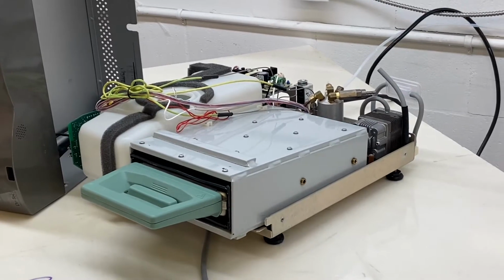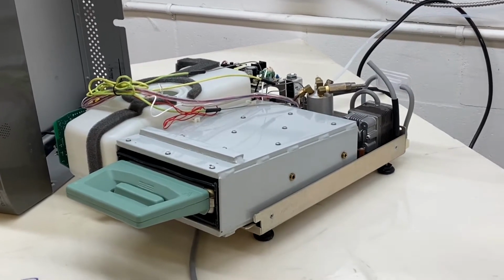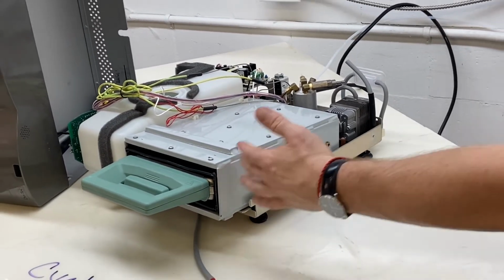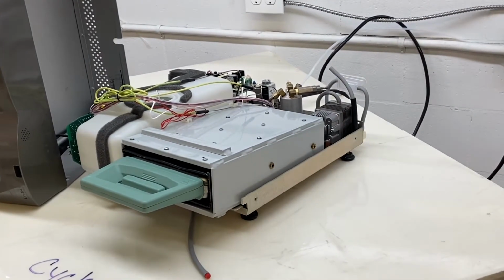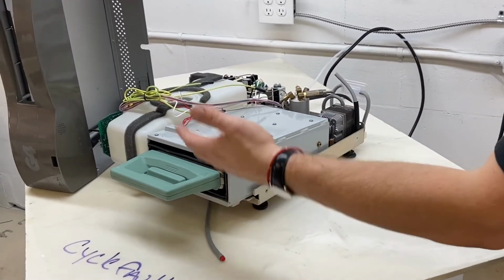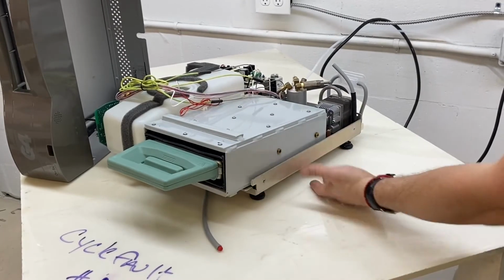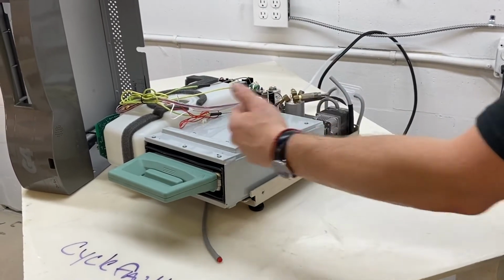So first, we are going to check for visible steam leaks from the cassette. You're going to see on this particular one, if it's in sterilize, you're going to be seeing little wisps out. You're going to be maybe a little puddle. You're going to see very little leaks there.